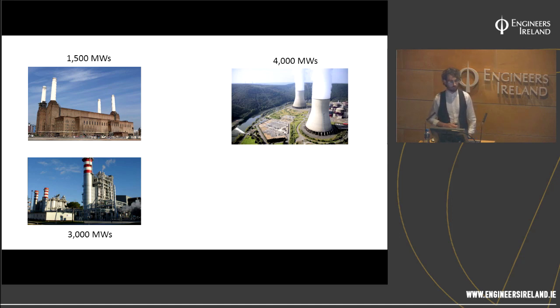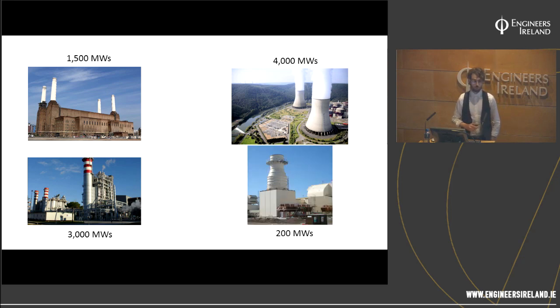Nuclear plants, which we don't have in Ireland, are typically higher again, around 4,000 megawatt seconds. And then a little peaker, a little open cycle gas turbine, comes in at a trusty 200 megawatt seconds. Now, these are all different for different reasons, and it's because of this equation here, which defines the stored rotational energy. That W rotational, the stored energy of a plant, is equal to the inertial constant multiplied by the apparent power rating. The apparent power rating is just the electrical size of the machine.